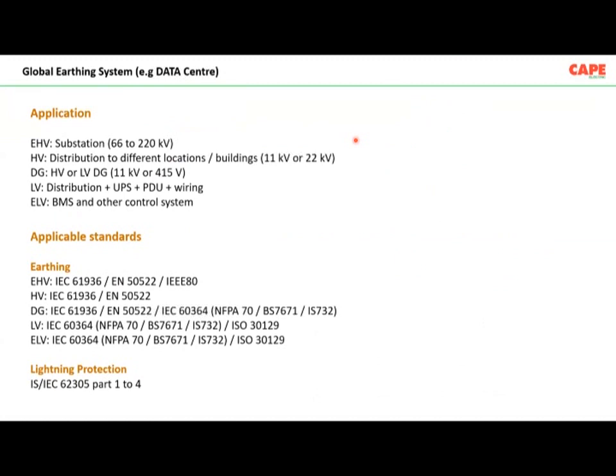Now, what do we do for modern buildings? For modern buildings, the recommended way of earthing is called global earthing. Global earthing is a typical earthing system which is achieved by interconnecting the earthing of extra high voltage, low voltage, your DGs, your UPS, ELV, and all these things together in a typical fashion so that the voltages are very much lesser.